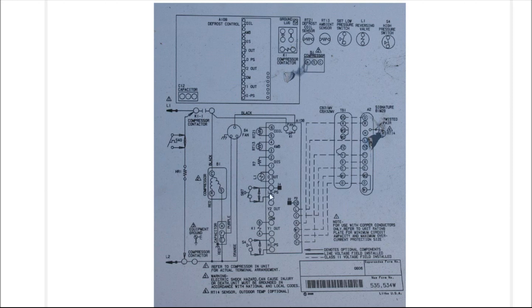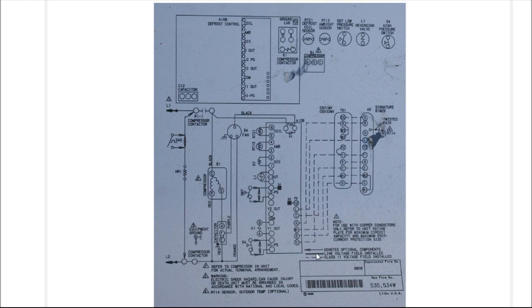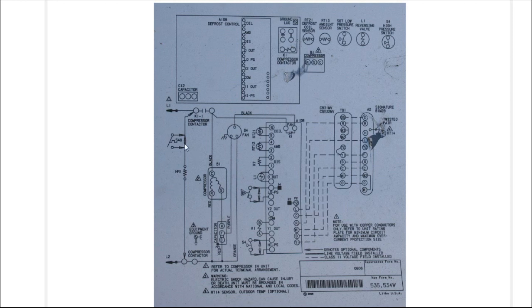L O dash P S is low-pressure switch, but the legend gives you more information than just the diagram down here. All of the legends will also have wiring information. The first thing to notice here is you have a triangle. Now this has nothing to do with wiring, but it does denote optional components that are in the system. So any component that has a triangle, for example the high-pressure switch, the low-pressure switch, and this happens to be the outdoor temperature sensor.